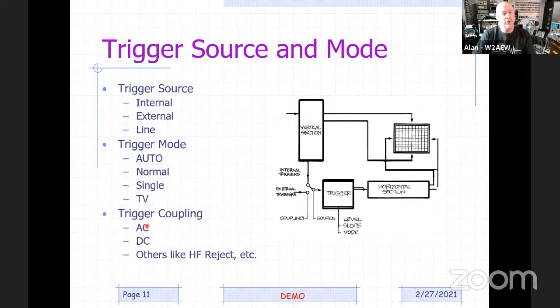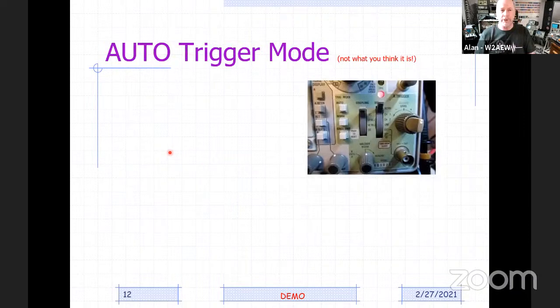And then similar to the vertical section and vertical controls, there's also trigger coupling. So you may choose DC reject or AC coupling of the signal into the trigger, so you're only going to trigger on a portion of the wiggle of the signal. You could do DC coupling, and sometimes there are other features like high frequency reject, but all that becomes pretty scope dependent. The digital scopes will have a lot more trigger choices available as well. But most of the time you can use a very simple trigger to get what you want. So again, the trigger really controls when that sweep is going to happen on an analog scope. On a digital scope, it more determines what feature I want to capture into memory to go analyze.